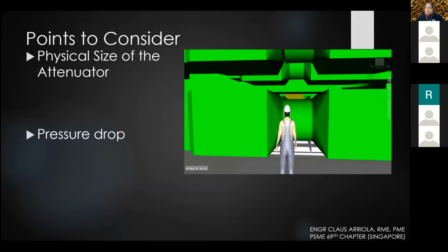Okay, I have designed in a depot with this large silencer. This is a fan from an underground MRT depot, wherein we have a large number of big ducts, big silencers and big fans. These fans are around 45 cubic meters per second. So it's a very, very big fan, around 2 meters in diameter. We need to consider the physical size of the attenuator, the silencer, and of course the pressure drop. Big silencer, big pressure drop.